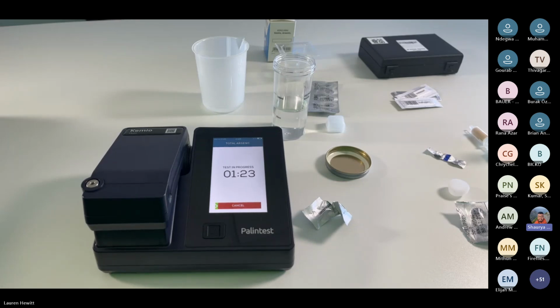So with the sensor alongside the buffer tablet, the device and sensor measure the chemical concentration using a technique called anodic stripping voltammetry, or ASV. Now this consists of 2 phases. In the first phase, the test applies a voltage to the electrochemical cell, and that draws any metals in the sample to the sensor. And once they have bonded, that is when the reaction begins. After that, the voltage is gradually changed, causing the metal ions to be released back into the water. Now, as those metals are released back into the water, that is when the current flows.